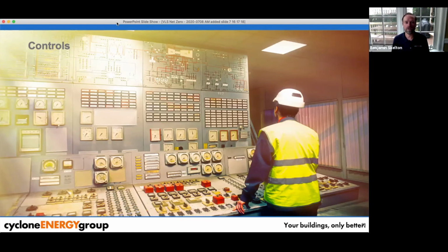And so I think getting to the next level of energy efficient buildings, we're not going to be doing it through standard variable air volume design buildings. We need a much simpler controls approach to things. So we're working on a project in Orlando right now that's going to be a zero energy building, and again, it's a store where the operators aren't going to be sophisticated, trained engineers. They need to understand that we want the temperature and the thermostat set at this. We want to maintain control, and we want the natural ventilation louvers to open when the conditions are correct, but it all needs to be simple enough for someone to operate.